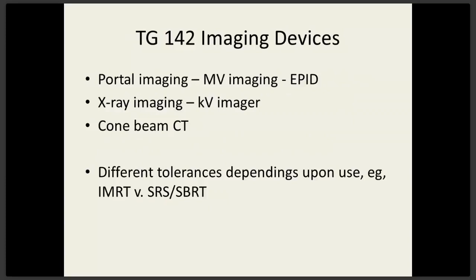And they also differentiated TG142, which was like an addendum to TG40, made the criteria more strict for SRS and SBRT machines because the stakes are very high with single dose or hypofractionation. So the tolerances are even tighter for SRS machines. 1 millimeter shifts, if it's going to be used for SRS, it has to be within a millimeter for SRS.